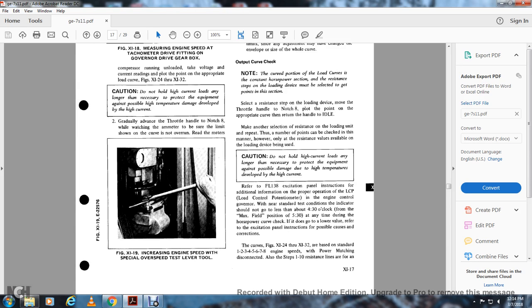Should not hold the high current loads any longer than necessary, to protect the equipment against possible damage due to the high temperatures developed in the high current.